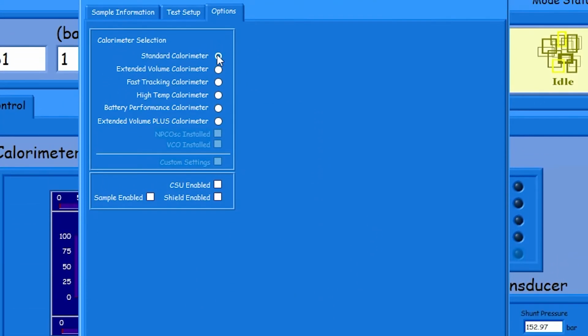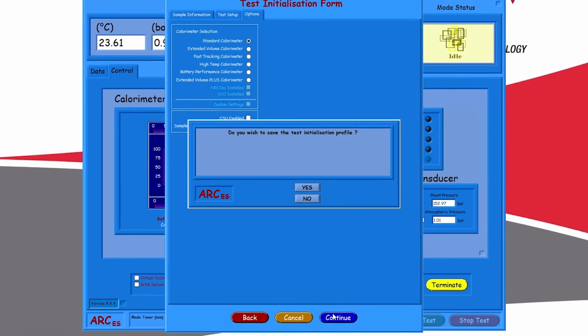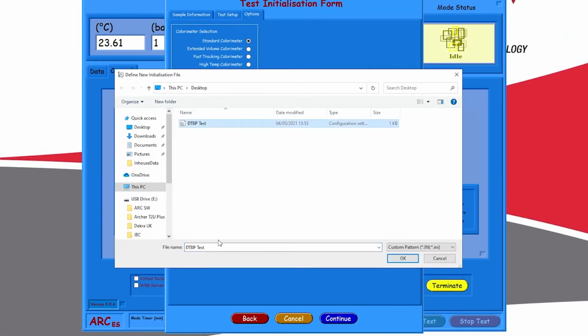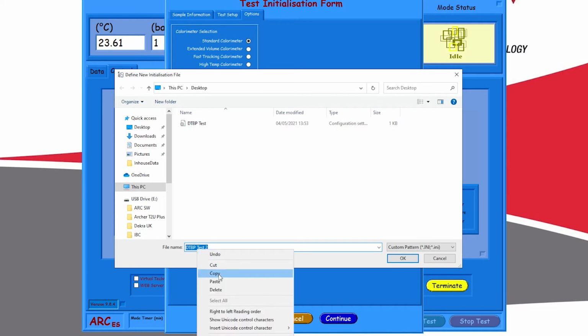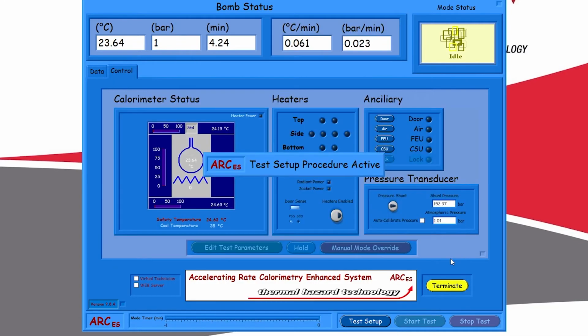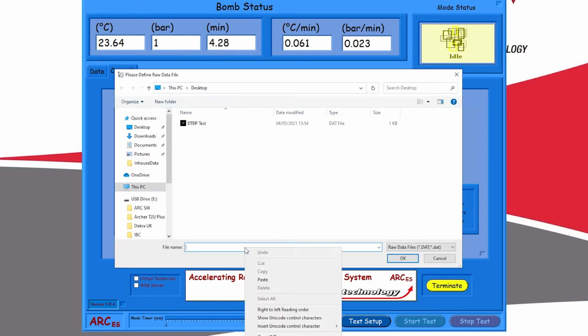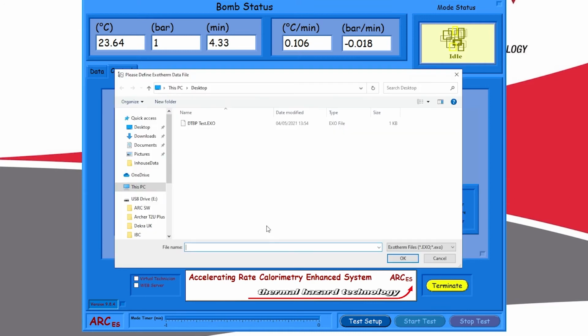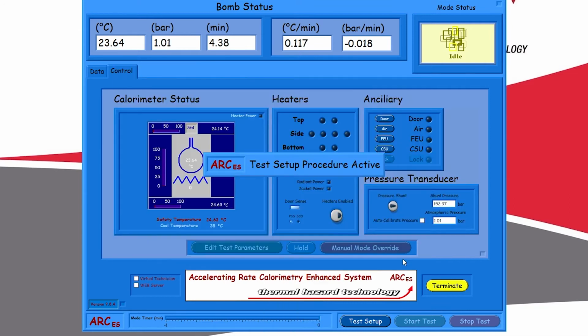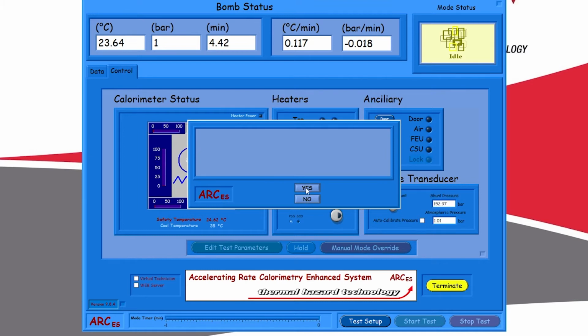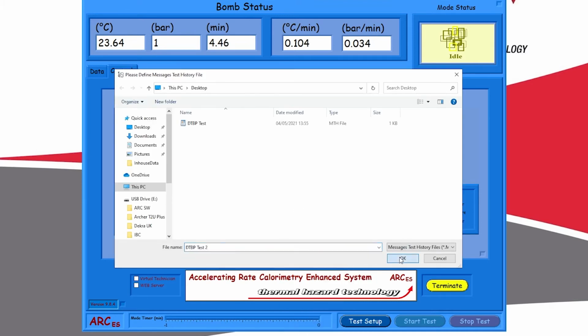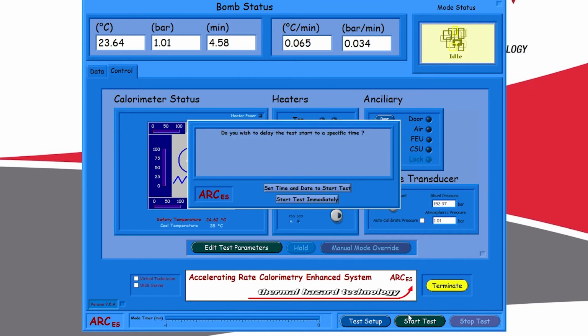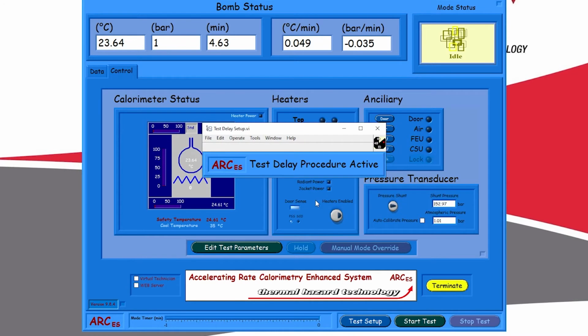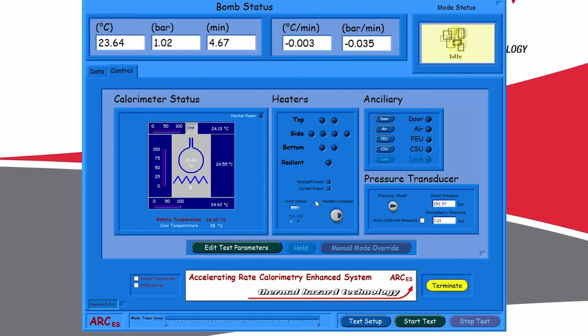Continue to the Options tab and select the calorimeter type. In the ARCes, only the standard calorimeter is used. Press Continue to open dialog boxes to name the various files generated in the test and choose where to save them. Once all files are saved, press the Start Test button and choose to start the test immediately. The test will start as indicated by the software showing heat mode in the top right of the software window.